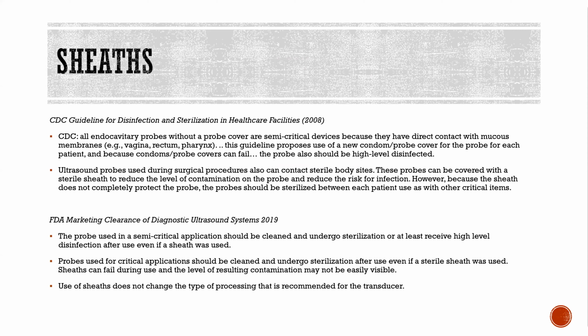The CDC recommends that all endocavity probes without a probe cover are semi-critical devices because they have direct contact with the mucous membranes. And so they propose that a new condom or probe cover is used for each patient. And again, even with that cover, the probe should still be high level disinfected.